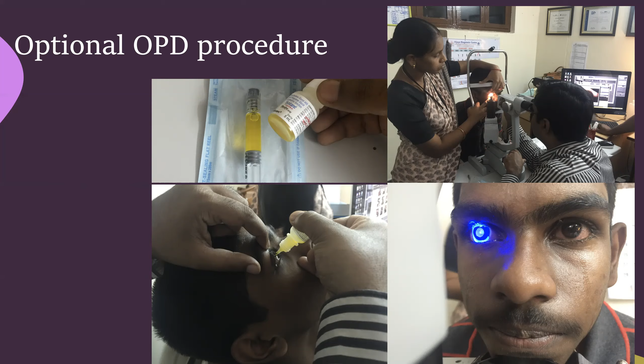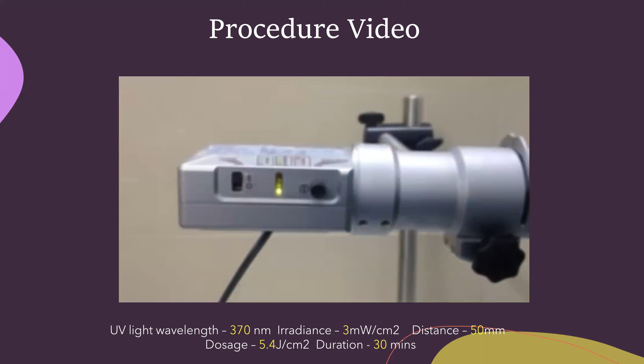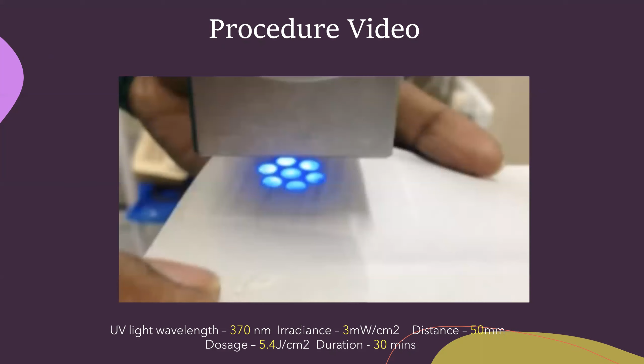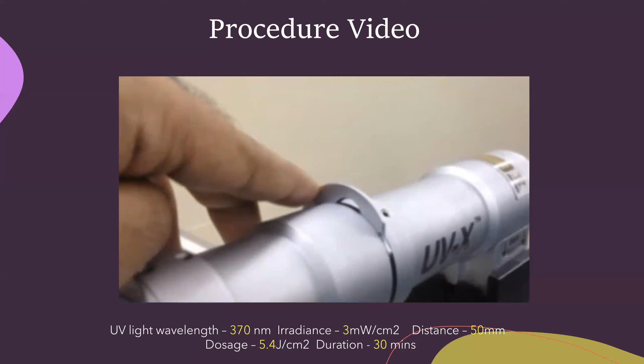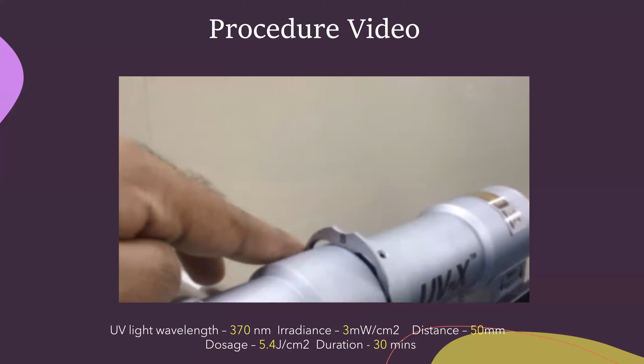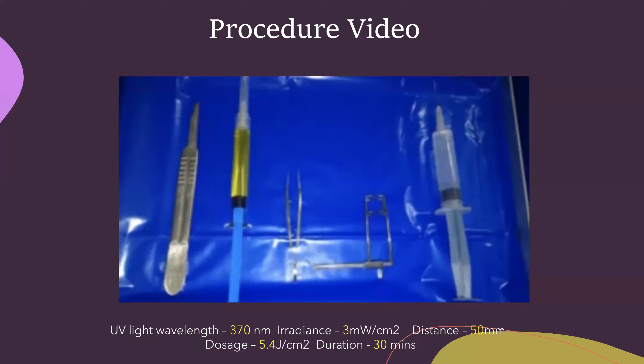So this is a small video, and the wavelength we use for the UV light is 370 nanometers. The irradiance is 3 milliwatts, and the distance is 5 centimeters from the corneal apex. The dosage is 5.4 joules, and the duration is 30 minutes. So before every procedure, make sure you calibrate the machine. When you're calibrating, keep it in the large aperture. The machine we are using here is the UVX, the initial one got by Dr. Saylor. And so these are the simple instruments that you need.